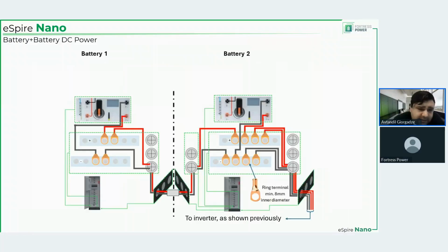Now, how to connect two batteries in parallel to one another. Each of them has its own battery management module, right? And just like before, that battery management module or unit connects to the bus bar of the same battery cabinet that contains this battery management module. So plus to plus, minus to minus. Same for both, right? So plus to plus here, minus to minus right here. The connection between the primary or first battery and the inverter remains the same as before. Nothing changes there. But you are now introducing two cables, one positive and one negative.